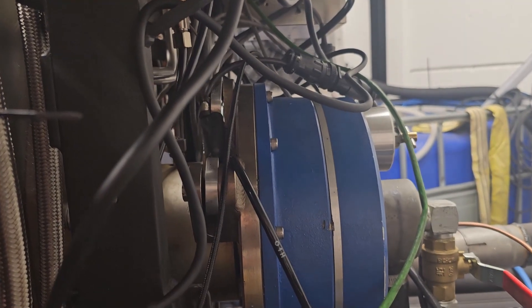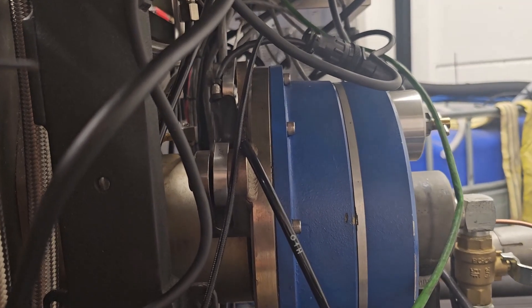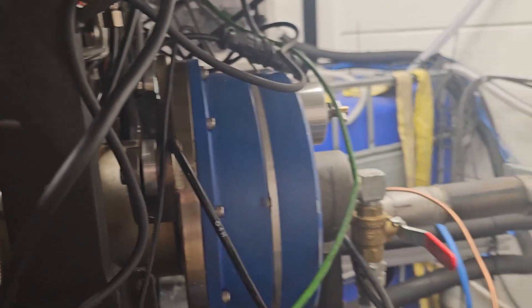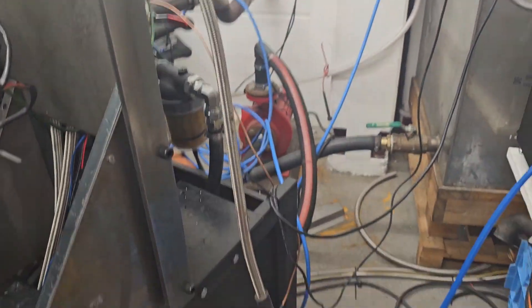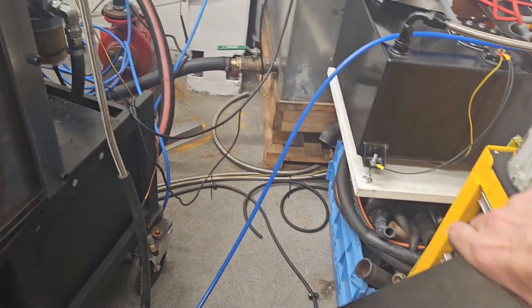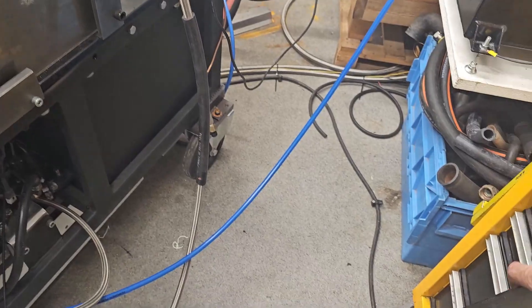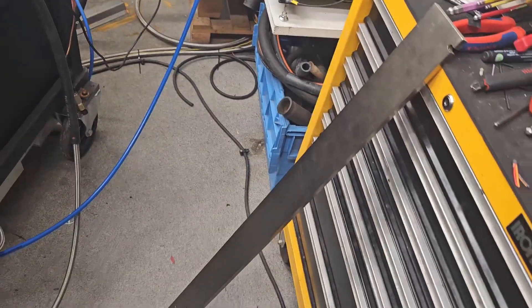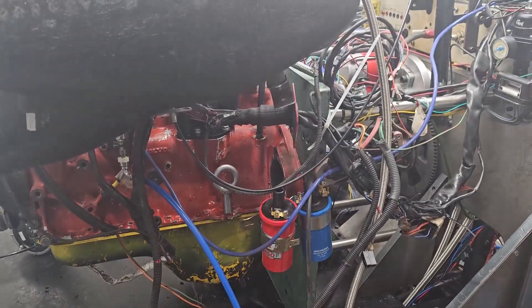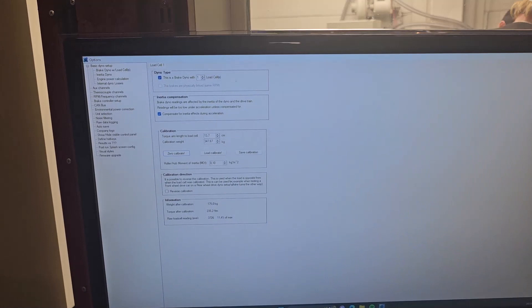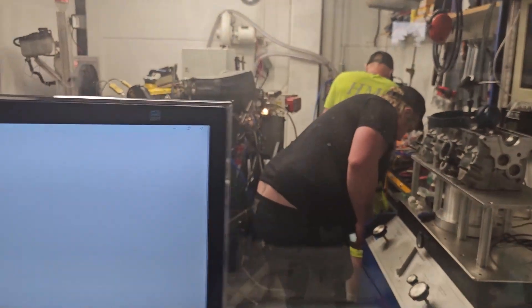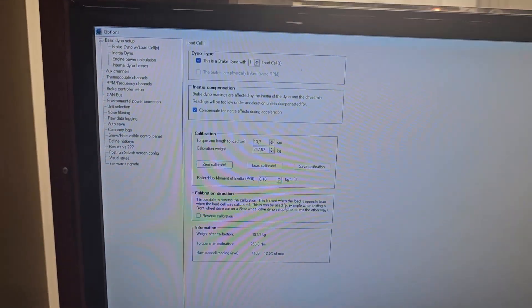So the load cell is in here, it's the original load cell that we have hooked up and we are going to do a calibration with this calibration arm that we have here. So first we'll do a zero calibration. We are calibrating, putting all the load on top of the calibration arm.